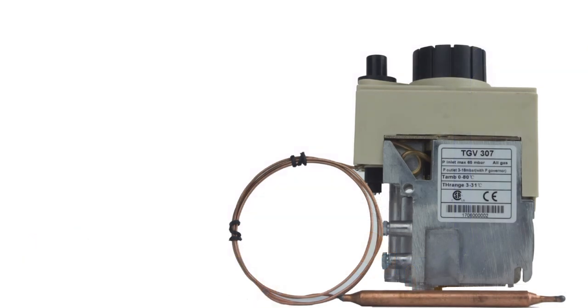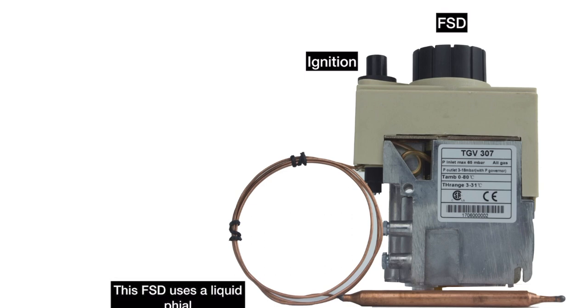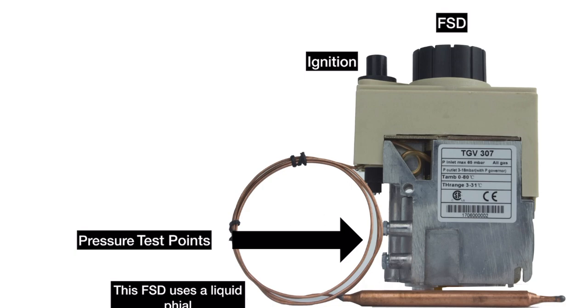Now, here's an example of a multifunction valve. There's your ignition on this one. You press that, it'll click, looks like a piezoelectric, like the small lighters. This will be your FSD that you press and hold in and wait for 10 seconds before it allows the valve to stay open. On this particular valve, it uses a liquid phial FSD, and you can see the phial and all the capillary tubing attached to the valve.